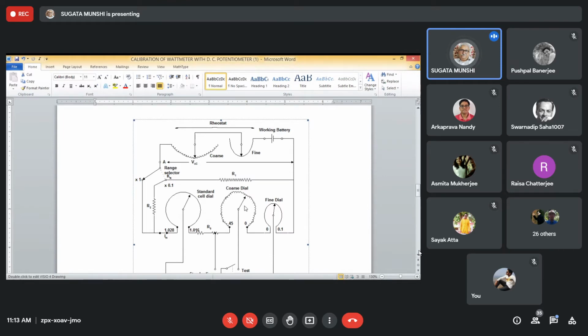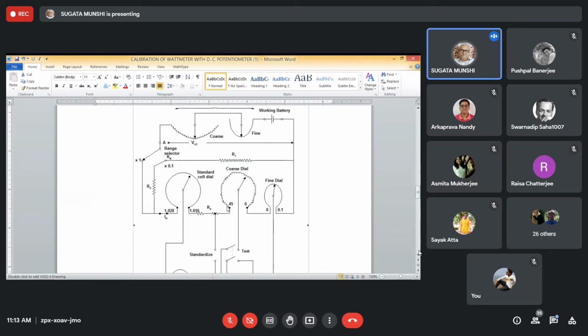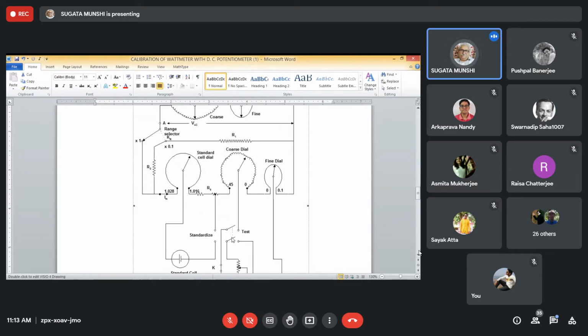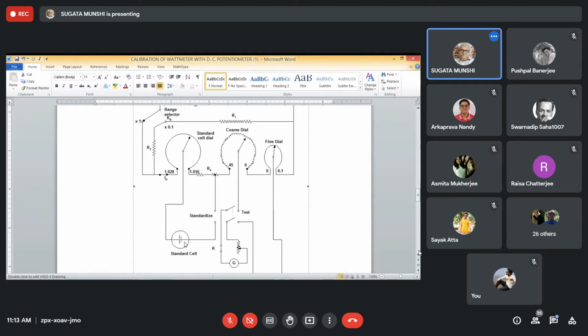Not by reading any ammeter. What is done in the standardization phase is that the switch is placed in the standardized position, so the standard cell gets connected to the potentiometer circuit. The standard cell is a cadmium cell - cadmium sulfate, mercurous sulfate, etc., as you have studied - and it gives a very stable voltage of 1.0186 volts at 20 degrees centigrade.